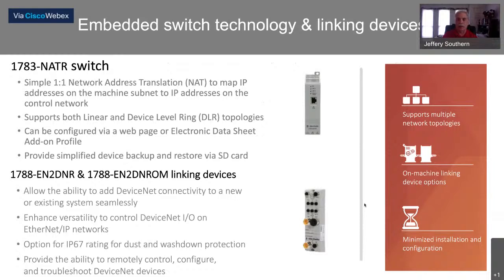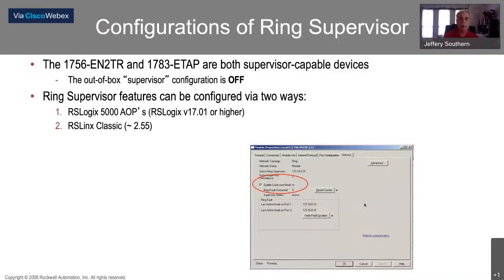A great use of this is with CompactLogix: you build a DLR ring to talk to all the devices, but you also need an IP address for the IT network. This ETAP gives you that by mapping internally the private address of the processor to the public address for the NAT. There's also a specific router built for it. The ETAPs are capable of being a ring supervisor - any ring protocol requires that the packet gets stopped somewhere around the ring, otherwise it would go around endlessly, so somebody has to be the supervisor.